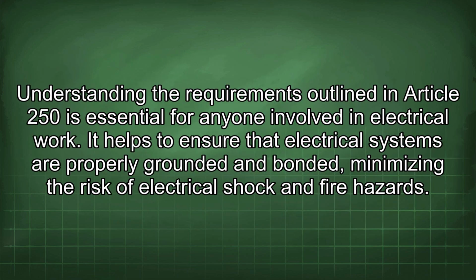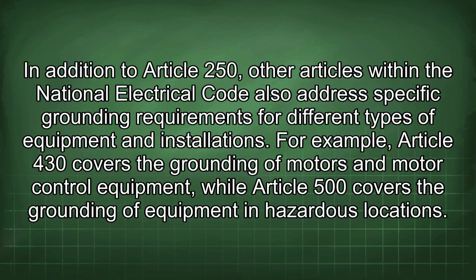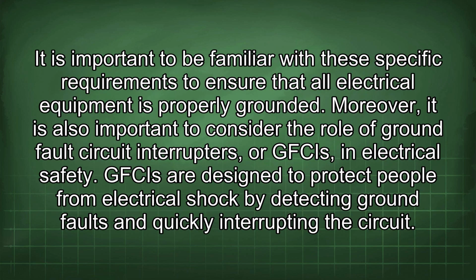Understanding the requirements outlined in Article 250 is essential for anyone involved in electrical work. It helps to ensure that electrical systems are properly grounded and bonded, minimizing the risk of electrical shock and fire hazards. In addition to Article 250, other articles within the National Electrical Code also address specific grounding requirements for different types of equipment and installations. For example, Article 430 covers the grounding of motors and motor control equipment, while Article 500 covers the grounding of equipment in hazardous locations.